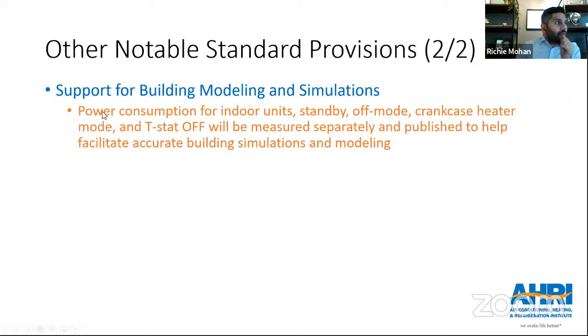Looking at it from a power consumption standpoint - the power consumption of indoor units, off mode, the crankcase heater, thermostat off mode - these will now be measured separately per this test procedure, and also published separately if you comply with it. Publishing these values from a power perspective should help effectively and accurately conduct modeling analysis for building efficiencies.